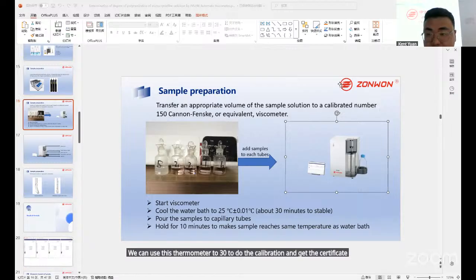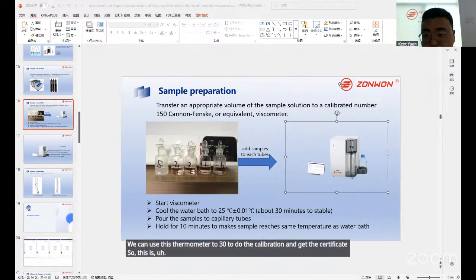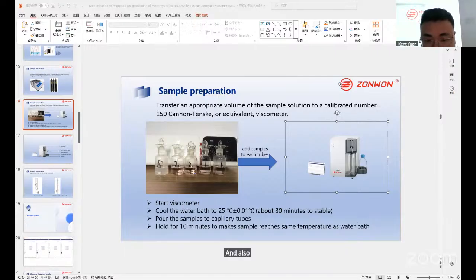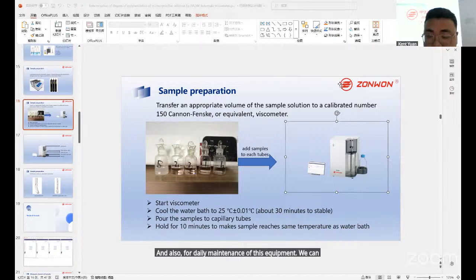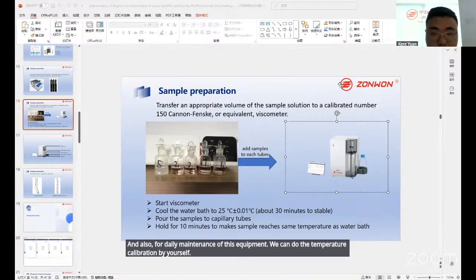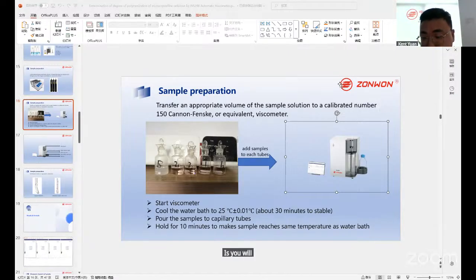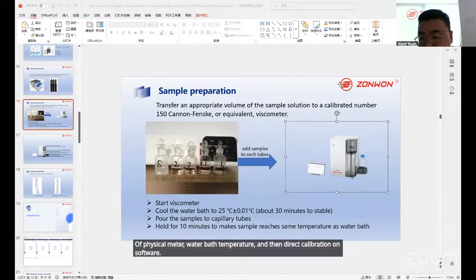So this is a calibration of the viscometer. And also for daily maintenance of this equipment, we can do the temperature calibration by yourself. We're using a certificate digital thermometer to check the viscometer water bath temperature, and then do the calibration on software.